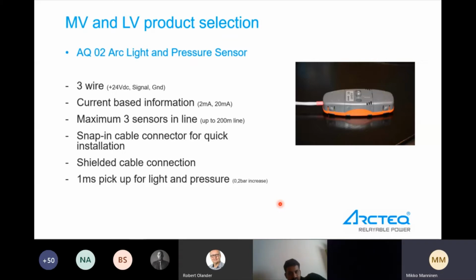Light and pressure sensor. This sensor type is sometimes or quite often used in the incomer cable section when there is no possibility to measure current before, or the current is measured after the cable connection, which is very typical. So if there is no possibility to measure current, this pressure can be the other factor of the logical AND gate, that we don't have current, but we have a pressure and light.